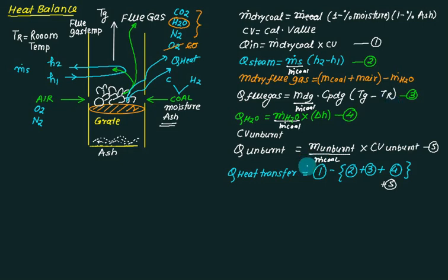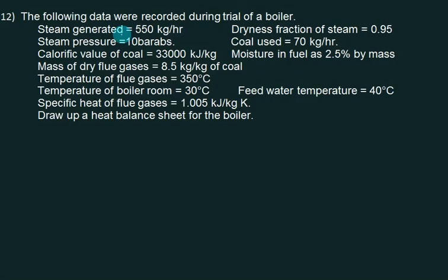Given data for the numerical problem: mass of steam generated is 550 kg, dryness fraction is 0.95, steam pressure is 10 bar, coal used is 70 kg, calorific value of coal is 33,000 kJ/kg, moisture content is 2.5%, mass of dry flue gas is 8.5 kg per kg of coal, flue gas temperature is 350°C, boiler room temperature is 30°C, feed water temperature is 40°C, and specific heat of dry gas is 1.005 kJ/kg·K.